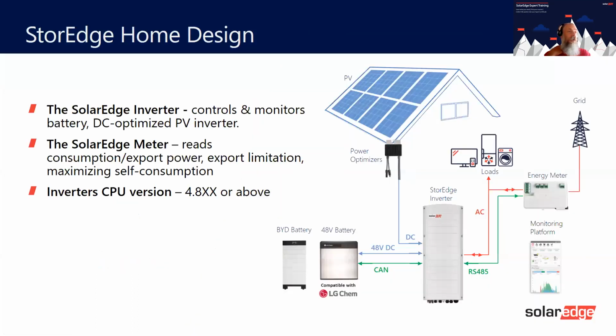So what does it look like? Well, we've seen this one here, but basically the meter reads the import, the export. It then communicates to the inverter. The inverter says, right, okay, we're going to discharge, tells the battery to discharge, and away we go. Or it gets the information from here that we're exporting, and then it says, right, we're going to charge from the DC, and so on. It tells you what to do. This is the brains here. This just gives information, but this is the brains.